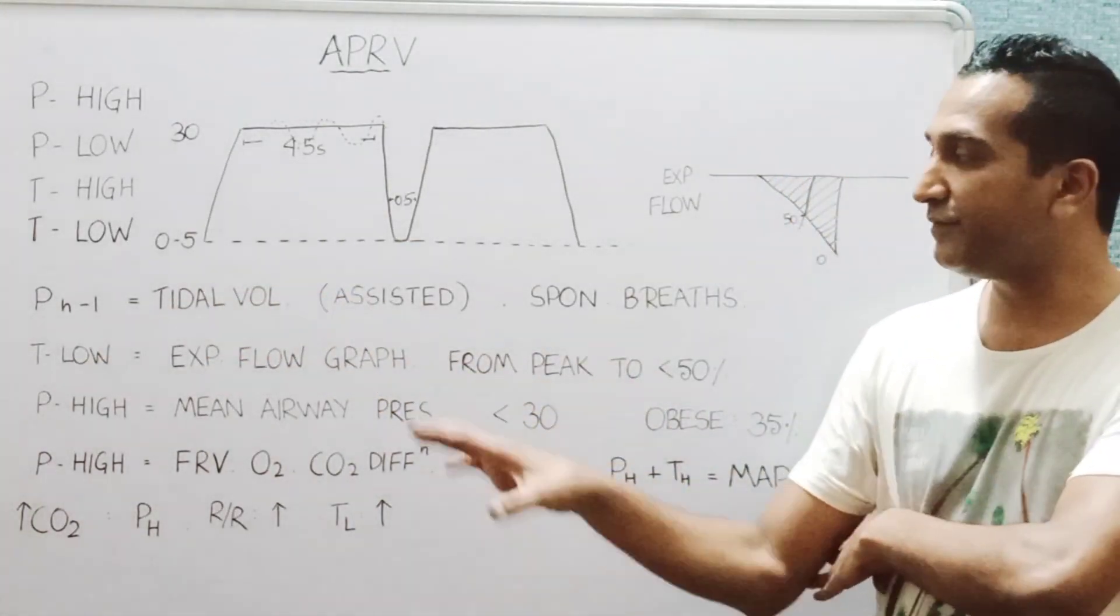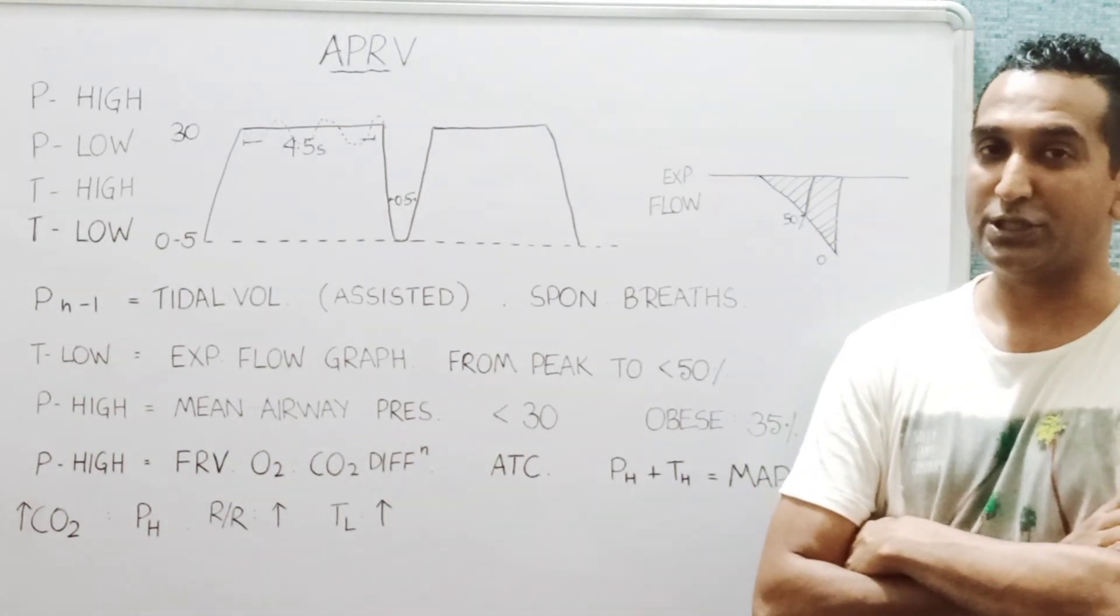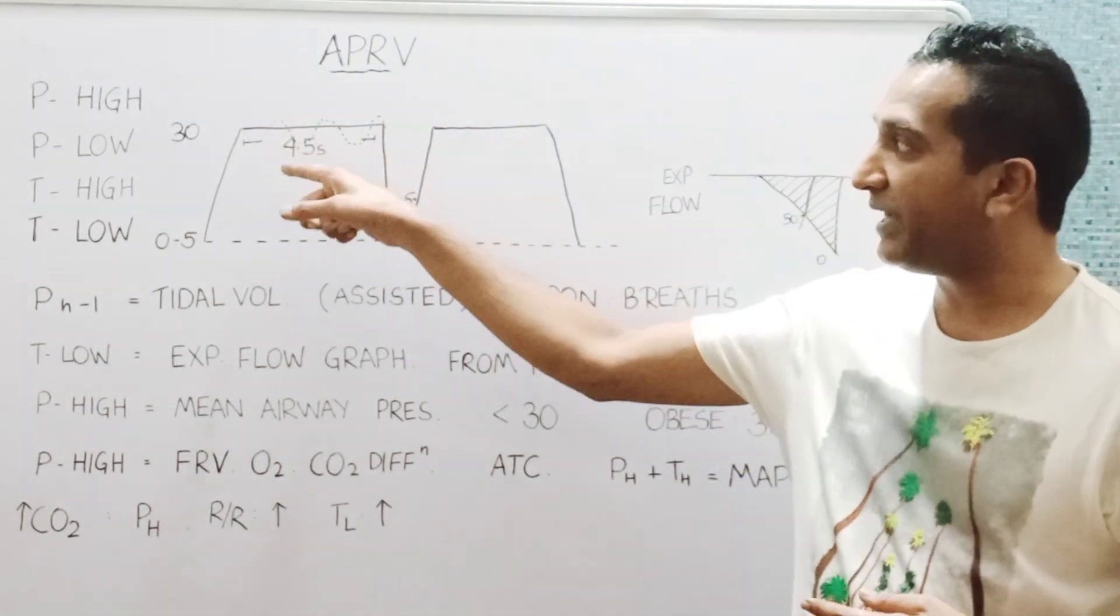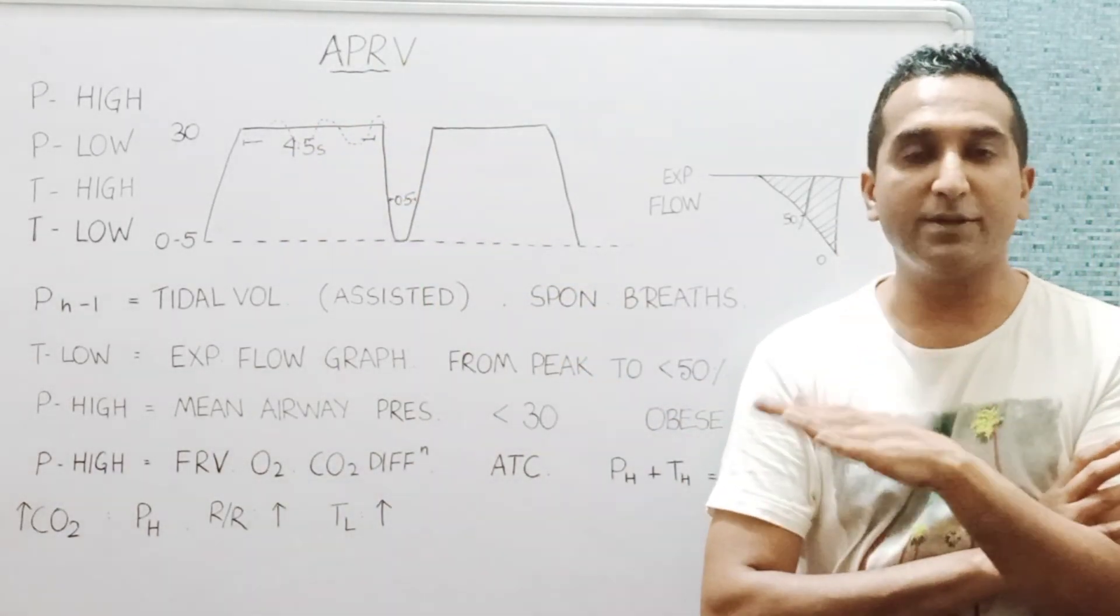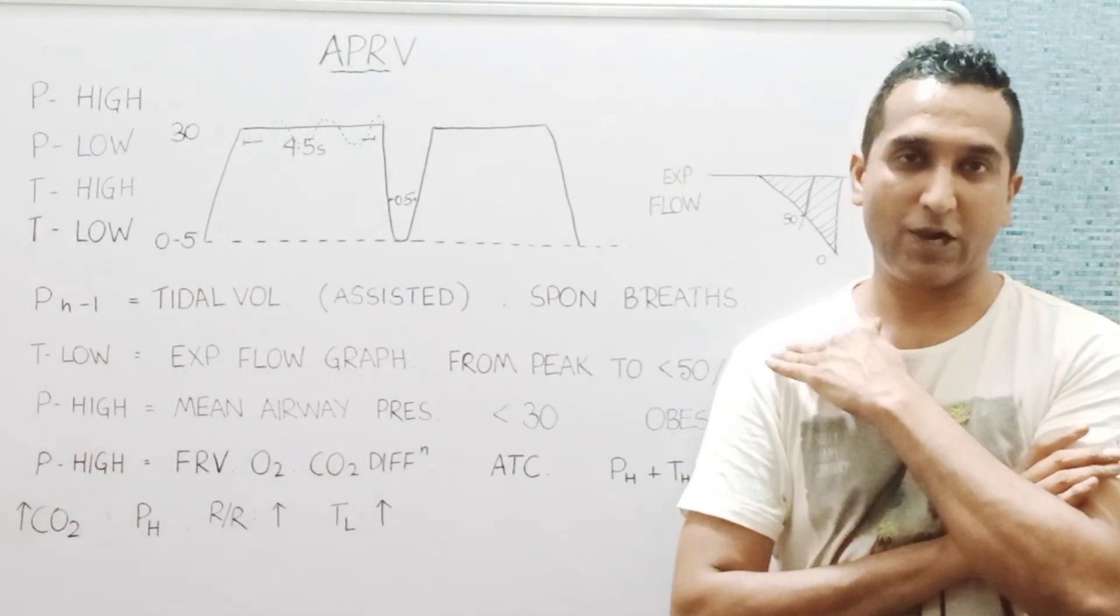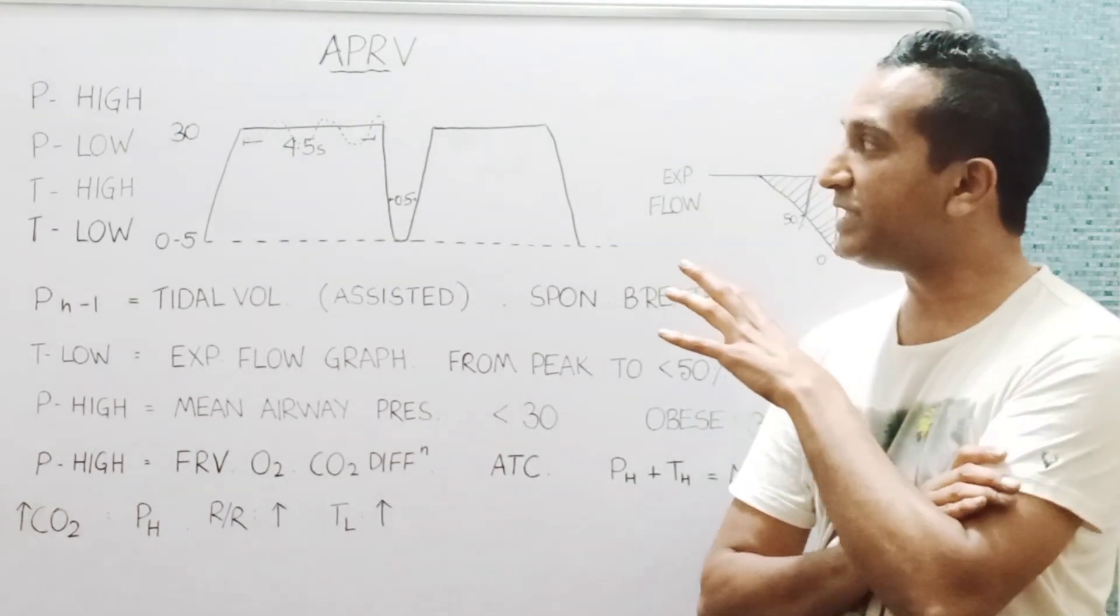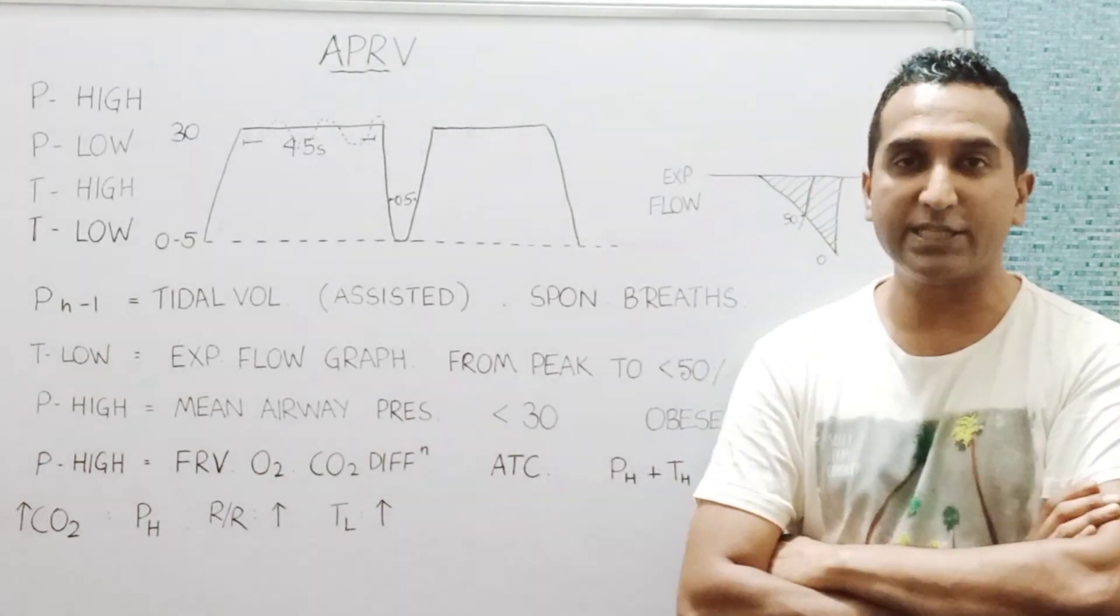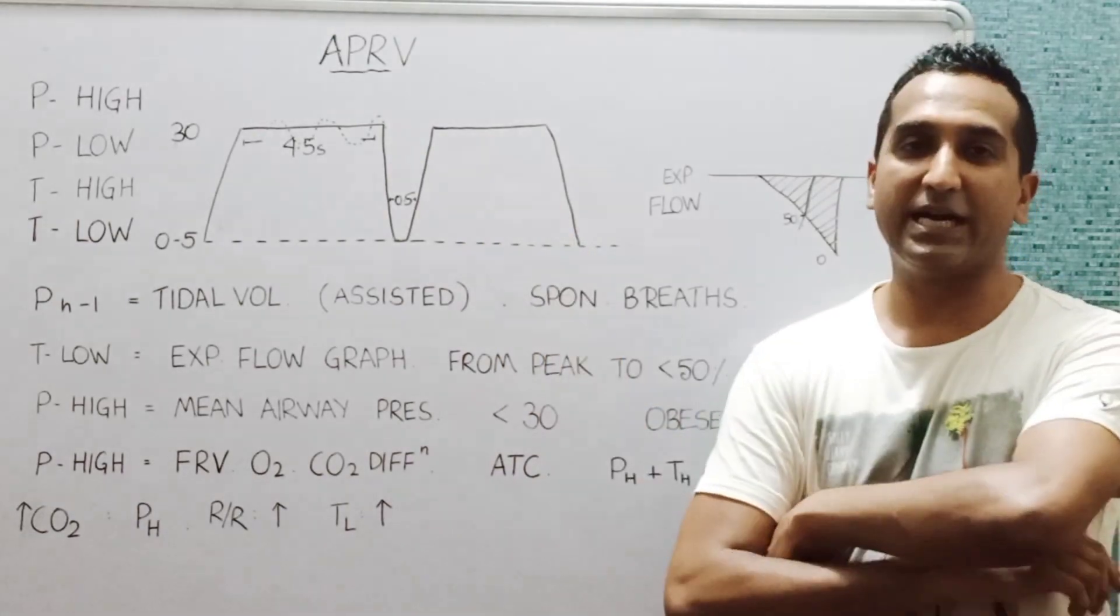The difference between the high and the low would determine the tidal volume, which is totally a ventilator-assisted breath, so there is no effort of the patient. Whereas at the P high, a dynamic expiratory valve allows the patient to breathe spontaneously.